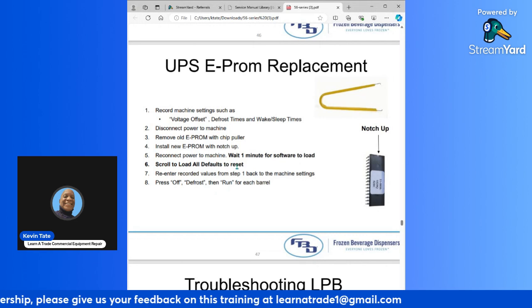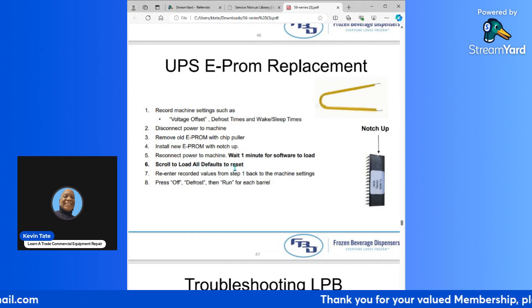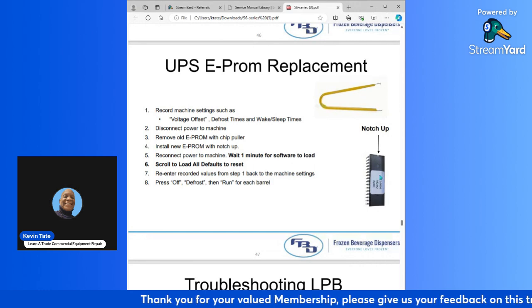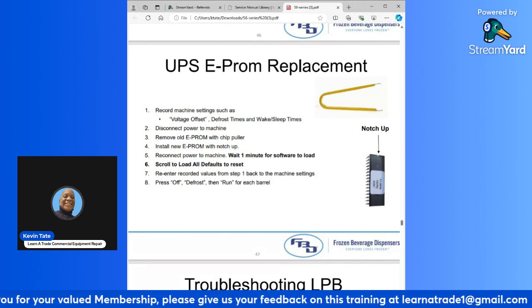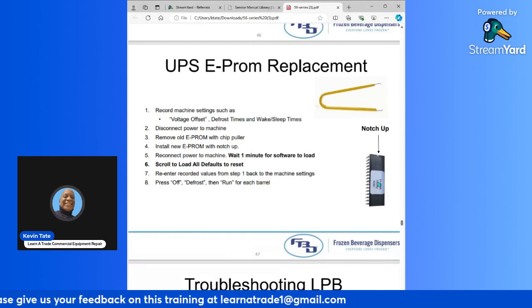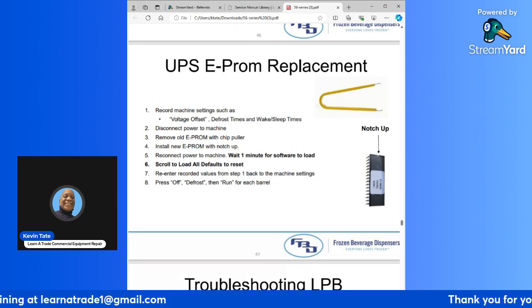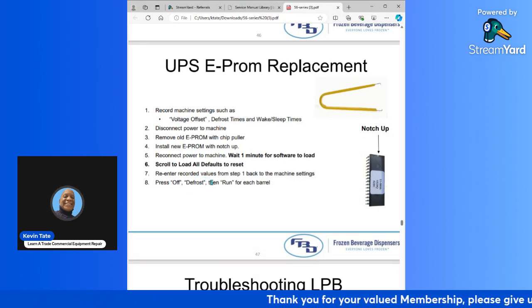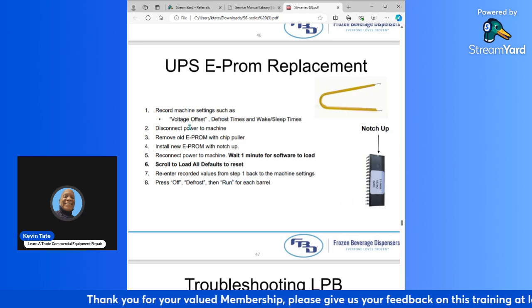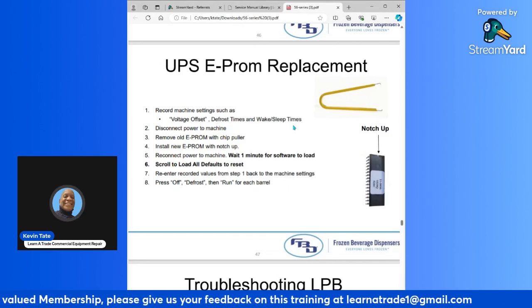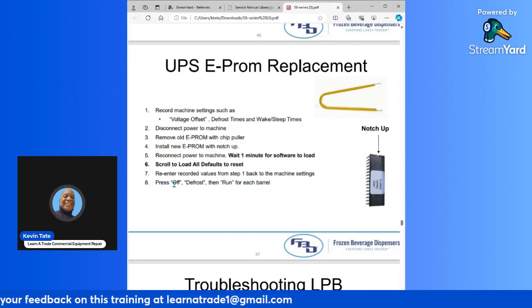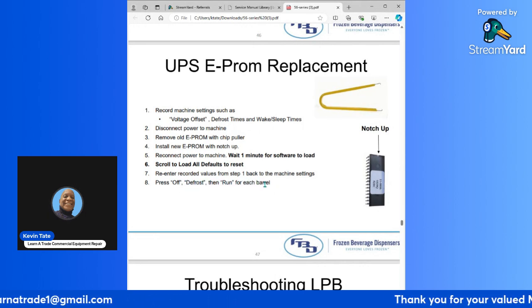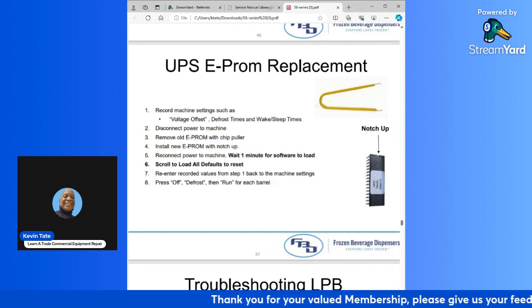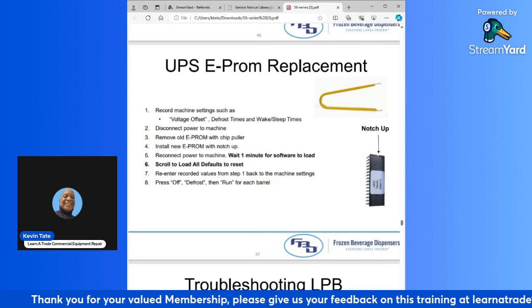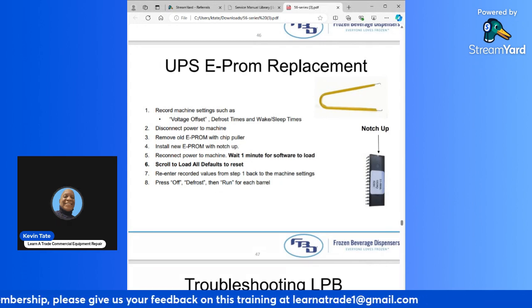Next, you would scroll to load all defaults to reset. This is a case where you would go to the end of that service menu and load all defaults, because you have a new chip in place and you want to reset it to the original settings. That's going to allow you to re-enter your recorded values from step number 1. So you're going to re-enter your voltage offset, your defrost times, and your wake and sleep if you had any. And then next you would press off, defrost, then run for each barrel. Each barrel will go through a defrost cycle, and then it will run, go into a freeze cycle, and all barrels should freeze down, and your settings are already loaded.